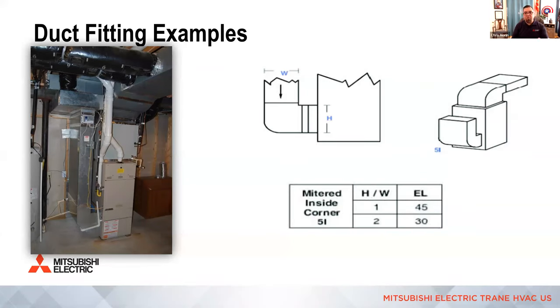Now, another typical fitting that we usually see on vertical systems, and this happens to be a furnace, but you can see is a right angle return drop. So that right angle return drop, if it's a hard 90 on the inside radius there, that's actually a 65-foot fitting. But if you have a mitered inside turn and it's a long sweep on the inside, you could reduce that to as low as 30 feet, more than half. So it's easier for the air to make that turn. It's less noisy, lower static pressures, right? And lower equivalent length value. So you could use smaller ductwork in that example.